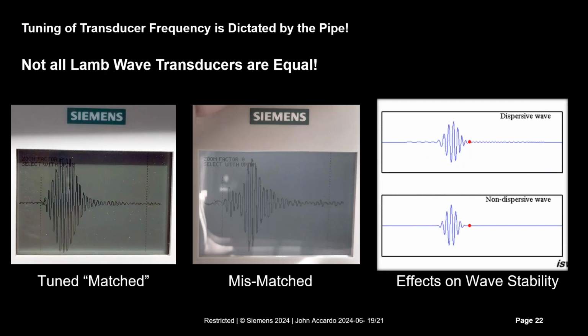So let's look at tuning the transducer. And again, on the right, you see that same graphic I showed you earlier about a dispersive wave and a non-dispersive wave. One of the nice things about the graphics display on the 1010 and now on the 230 is that you can actually see your transducer waveform. And the waveform on the left is a proper wave shape. You can see that there's a flat line to the left, and then there's a gradually increasing sine wave, which is the arrival of the sonic beam at the receiving transducer.